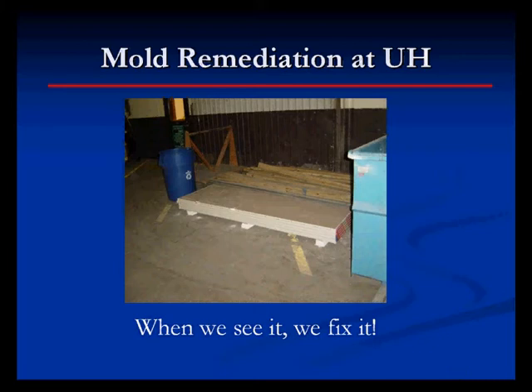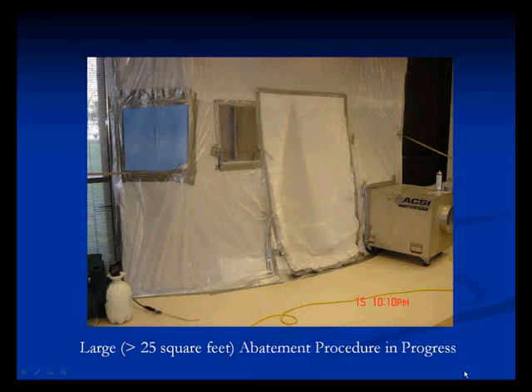This is the Plant Operations carpenter shop. You can see some new sheetrock, which could be used to replace a mold-infested area. The Texas Department of State Health Services has passed some rules concerning mold in public buildings. Basically, visible mold on surfaces larger than 25 contiguous square feet must have a licensed mold abatement company to perform a remediation. This is from a mold remediation project which took place in Science and Research 2.